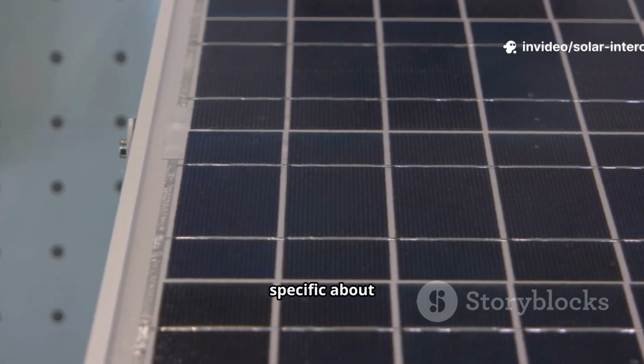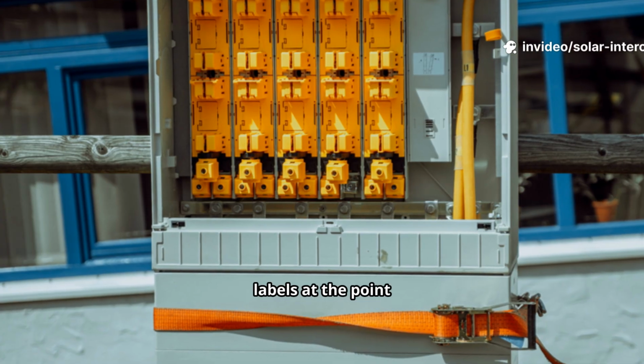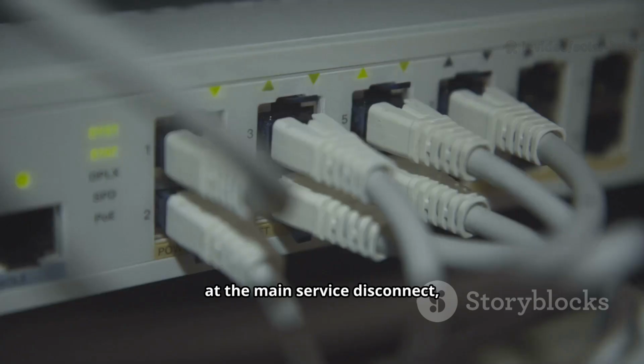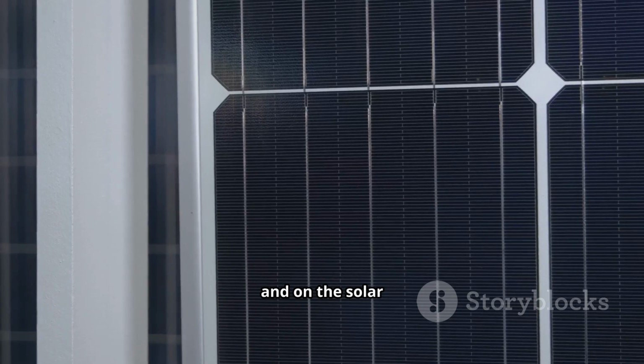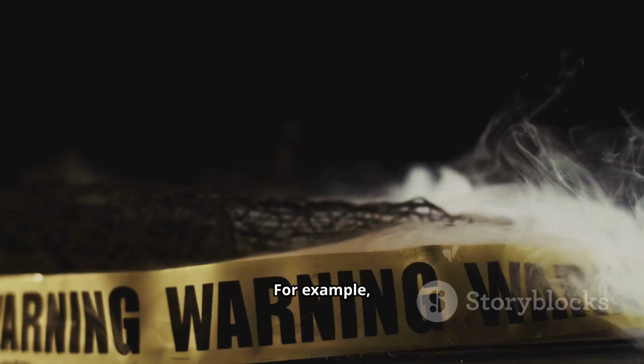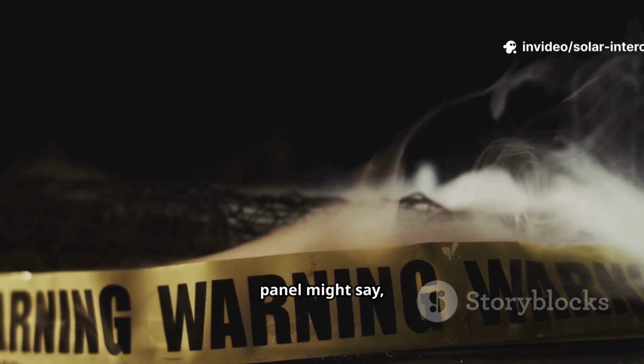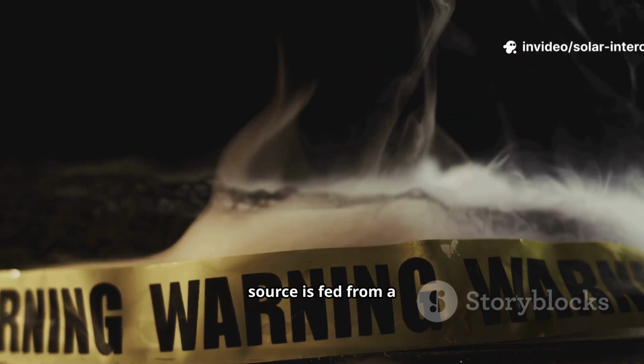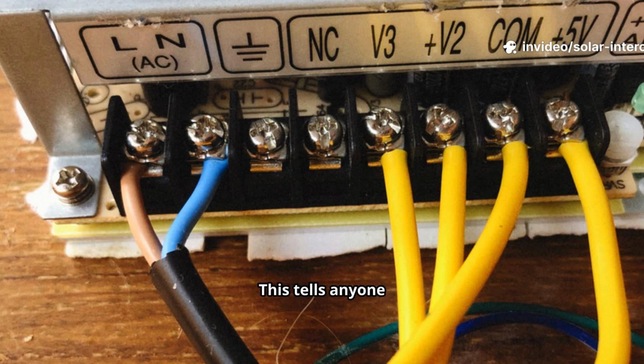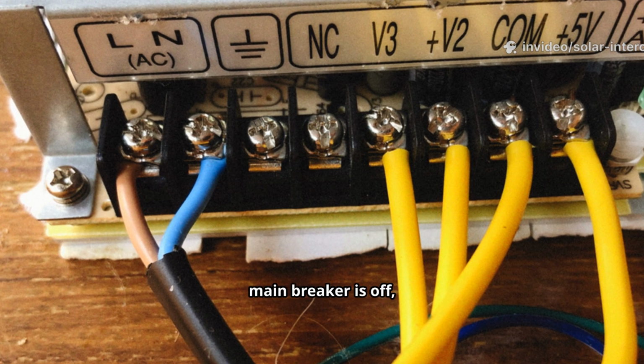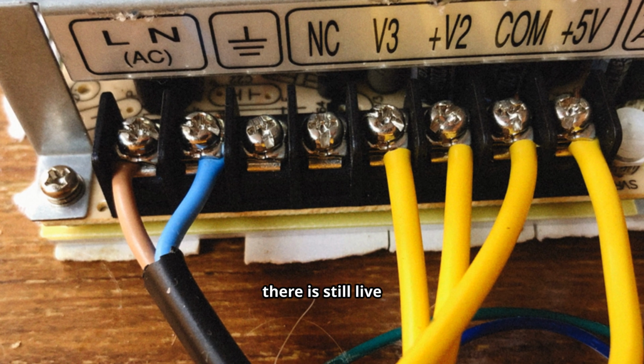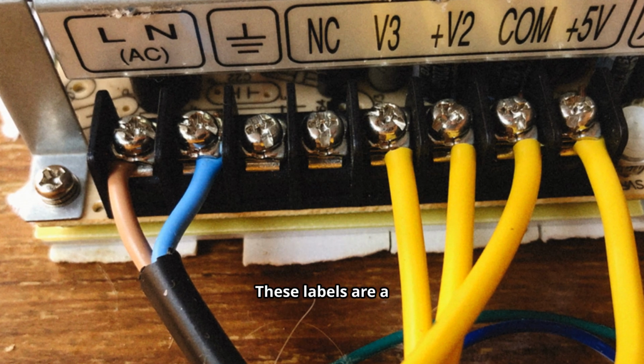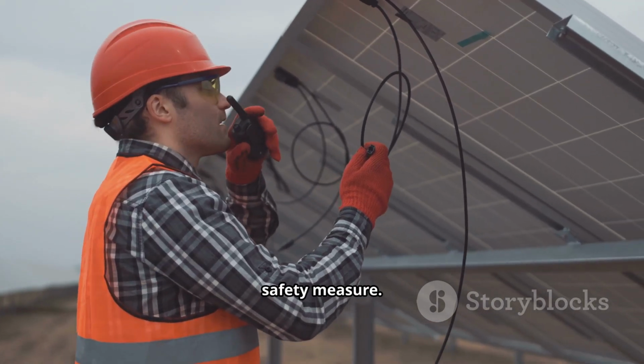Another example is the requirement for proper labeling. The NEC is very specific about warning labels. You must have labels at the point of interconnection, at the main service disconnect, and on the solar equipment itself. For example, a label at the main panel might say, "Warning, power source is fed from a remote source." This tells anyone working on the panel that even if the main breaker is off, there is still live power coming from the solar system. These labels are a simple but vital safety measure.